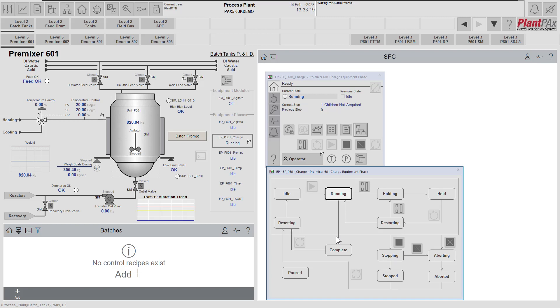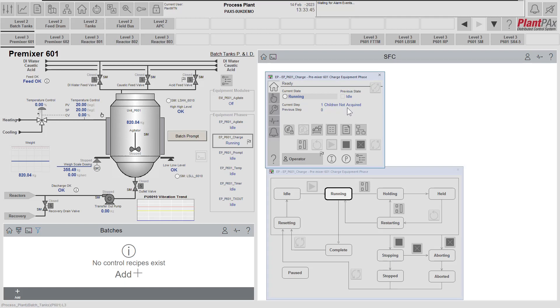The running state is now active in our controller and the sequence steps that our implementer has implemented in that running state are now executing. On the faceplate you can see that we are currently in step one of that sequence, and the implementer can also implement messages to be displayed for every step. Here we can see that the children are not acquired — this equipment phase has not acquired its children. The equipment phase framework uses the organization ownership and arbitration framework, which we discuss in detail in another video.